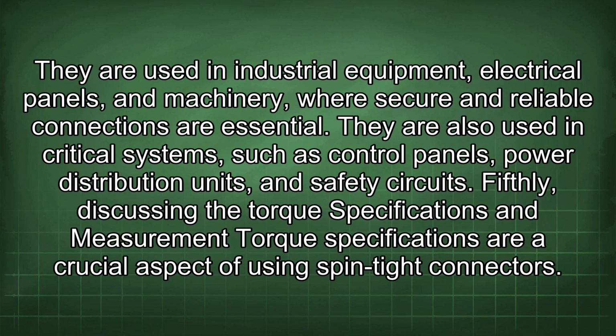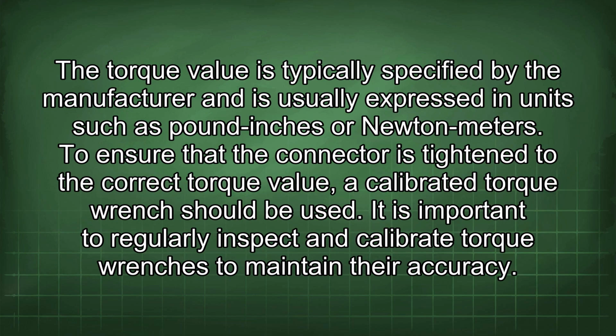Fifthly, discussing the torque specifications and measurement. Torque specifications are a crucial aspect of using spin-tight connectors. The torque value is typically specified by the manufacturer and is usually expressed in units such as pound-inches or Newton meters. To ensure that the connector is tightened to the correct torque value, a calibrated torque wrench should be used. It is important to regularly inspect and calibrate torque wrenches to maintain their accuracy.